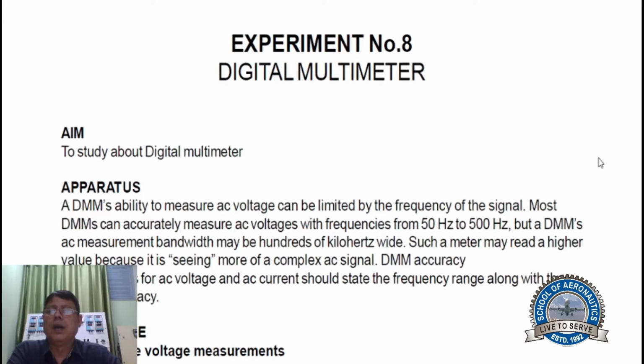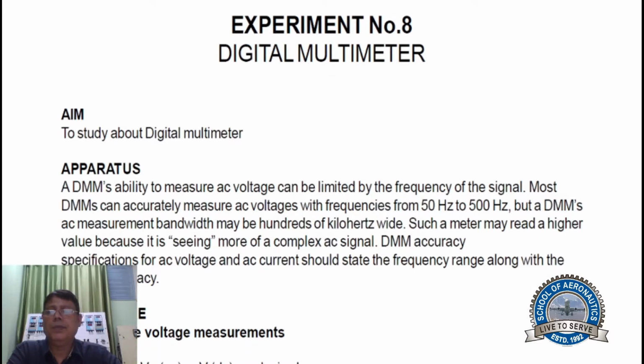A DMM's ability to measure AC voltage can be limited by the frequency of the signal. Most DMMs can accurately measure AC voltage with frequency from 50 Hz to 500 Hz. But a DMM's AC measurement bandwidth may be 100 kilohertz wide. Such a meter may read a higher value because it's seeing more of a complex AC signal. DMM accuracy specifications for AC voltage and AC current should state the frequency range along with the range of accuracy.